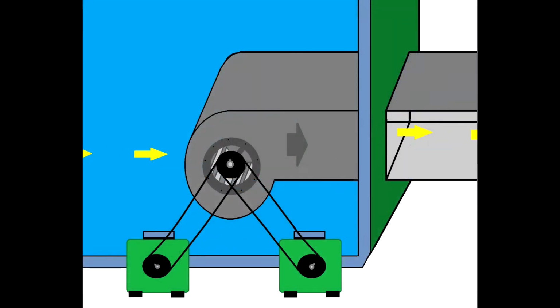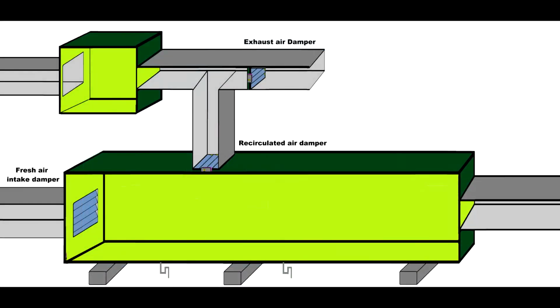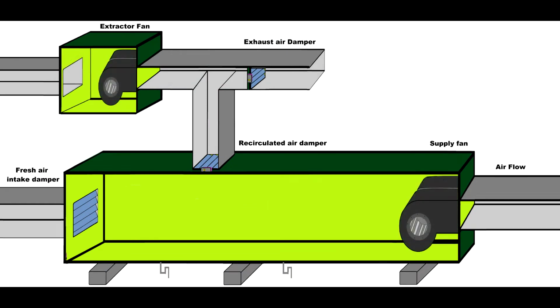Another type of fan you can use is a scroll but belt-driven one. Again, in this situation you'll have a negative pressure in the supply air chamber. I'll talk about this later on, but I think I had another YouTube video that talked about this in more detail. Coming back to our story, this is our box. It's an AHU. To circulate the air we need motors. To direct the air we need dampers.